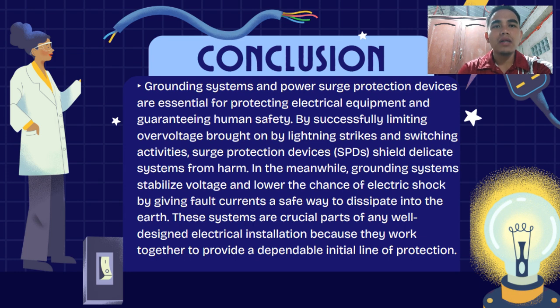A grounding system and power surge protection devices are essential for protecting electrical equipment and guaranteeing human safety by successfully limiting overvoltage brought on by lightning strikes and switching activities. Surge protection devices, or SPDs, shield delicate systems from harm. In the meanwhile, grounding systems stabilize voltage and lower the chance of electric shock by giving fault current a safe way to dissipate into the earth. These systems are a crucial part of any well-designed electrical installation because they work together to provide a dependable first line of protection.